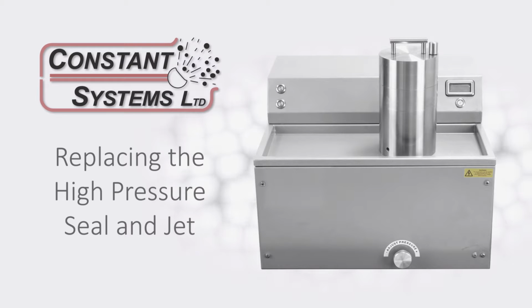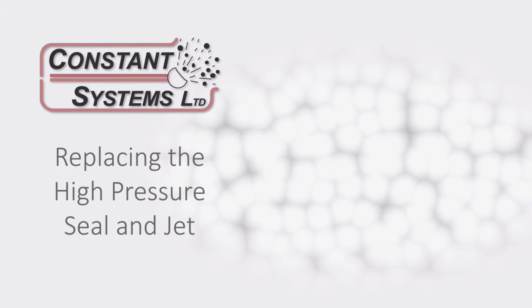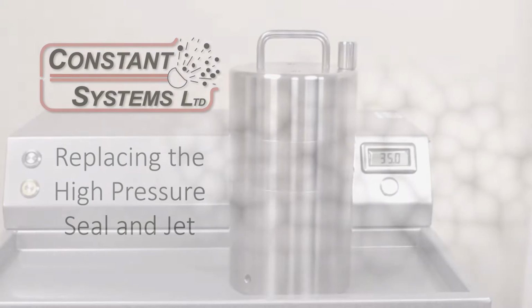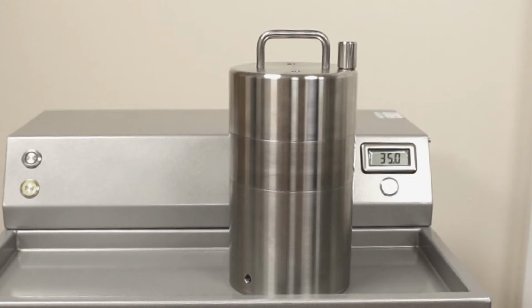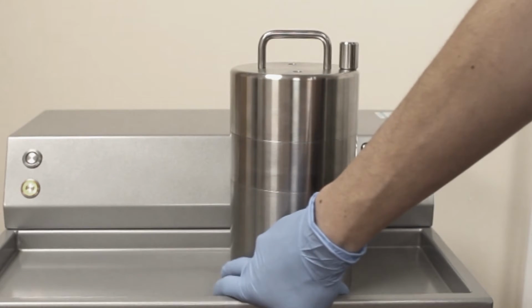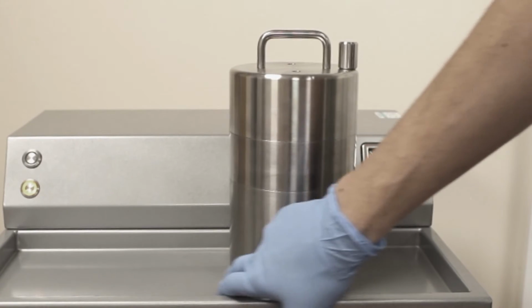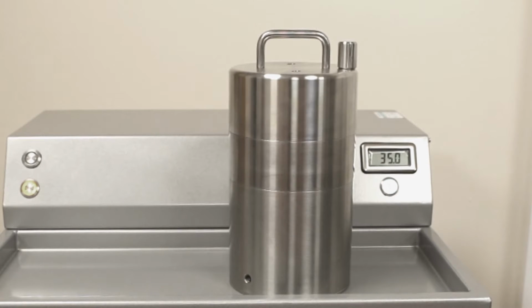The second half of the video is going to show you how to change some consumable items, namely the high pressure seal and the jet. The high pressure seal should be changed every 10,000 strokes. The multi-cycle and one-shot machine does not have a counter fitted, so it's vital that you make use of the logbook provided. If you're noticing a leak of liquid from either of these two ports here at the base, this means that the high pressure seal is leaking and needs to be changed.